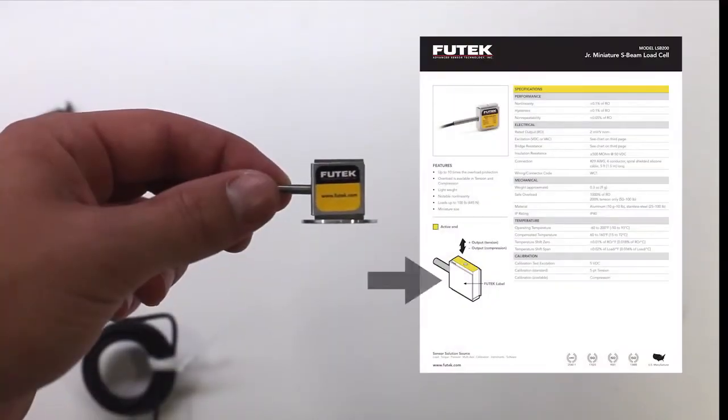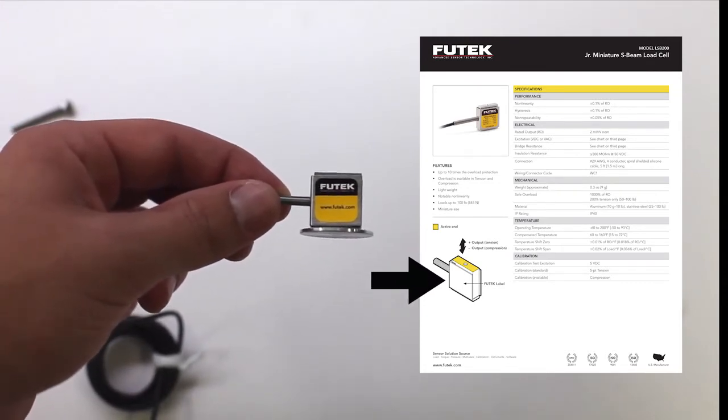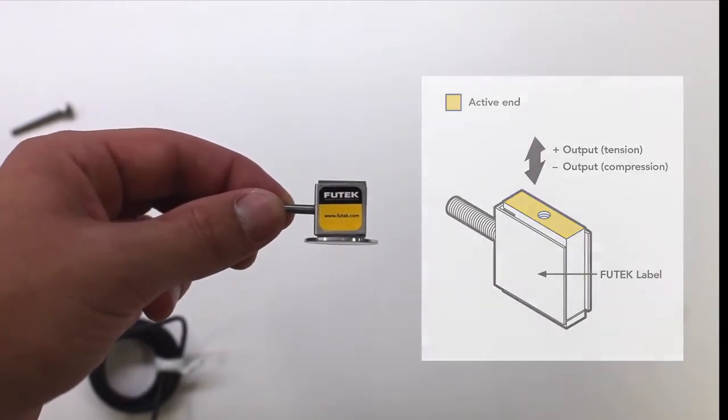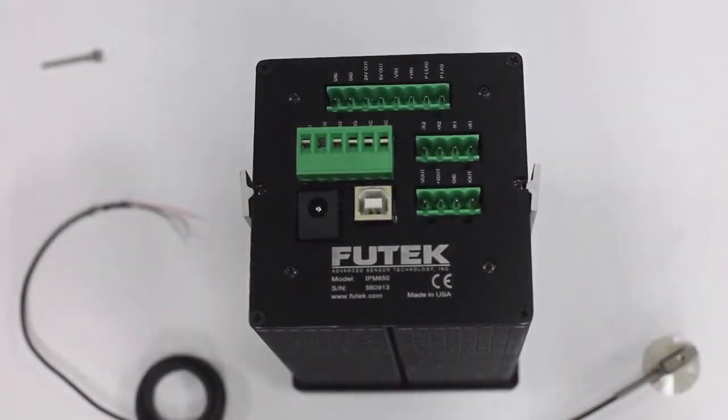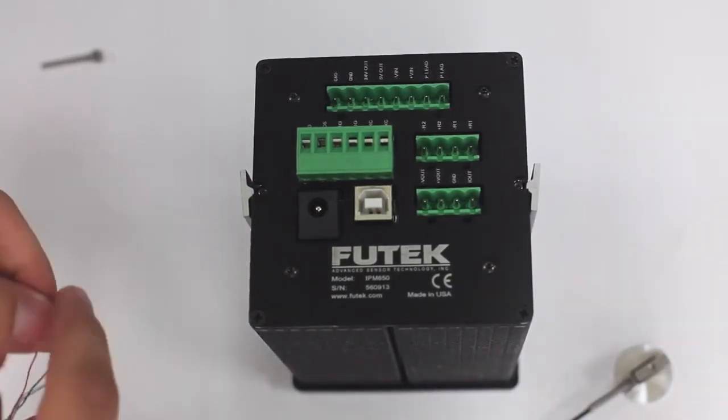It is important to note that the LSB200 and many other Futek load cells have a designated loading surface. This is specified in the sensor spec sheet. It is also important to monitor the load cell's readings during the installation process to see if we are applying any unintended loads. We can do this using an IPM650.